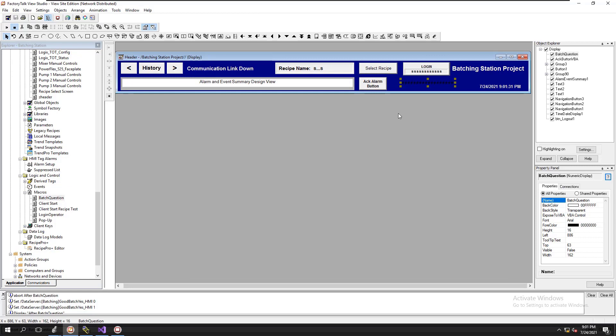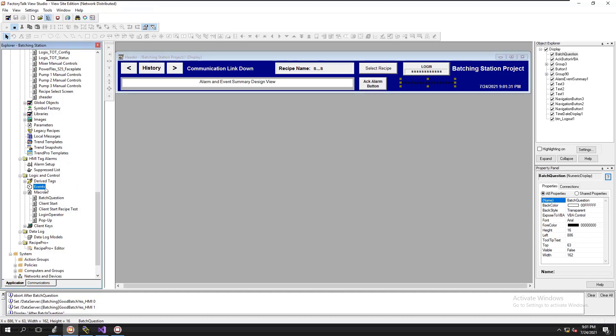So with that said, the way to properly execute a pop-up is to have a hidden numeric display element, have that numeric display trigger the VBA code control, and in the VBA code write a small script. That's a good solid way to make a pop-up screen inside of FactoryTalk SE. It doesn't matter what version you're on — version 5, 6, 7, 8, 9, 10, 12 — any FactoryTalk SE Site Edition version. That is the best way to do it with VBA code without such a headache. I have heard of people using events, but events tend to have problems. The VBA code approach is the best way based on everything I've seen. So I wanted to share this detailed video and spread the knowledge as much as we possibly can. We'll see you on the next one.